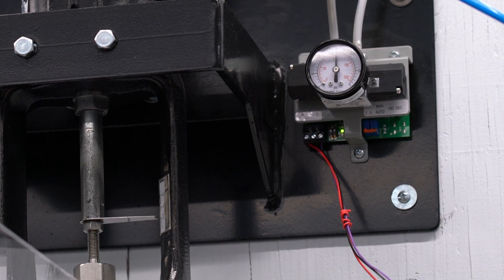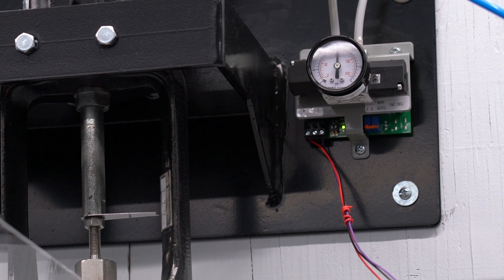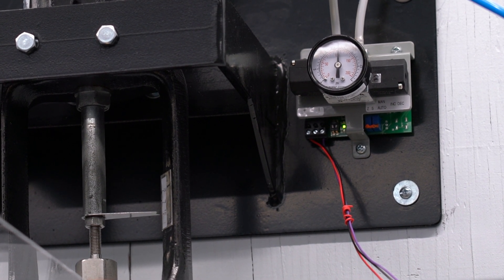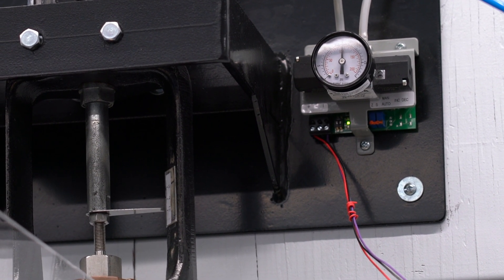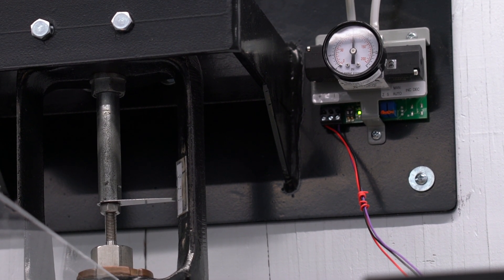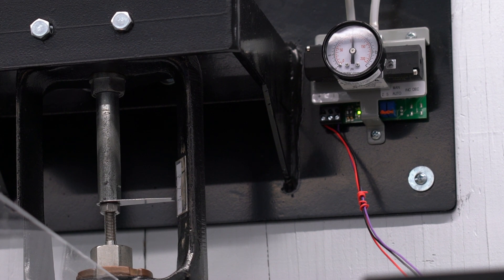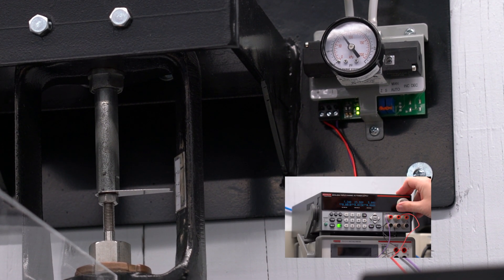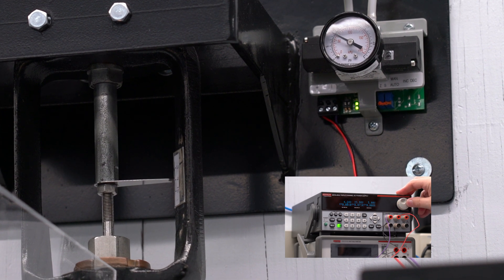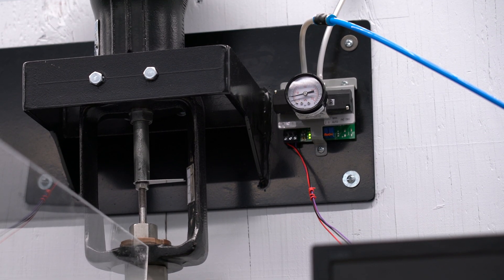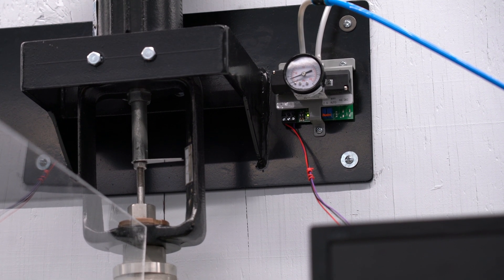Now the other thing is there's a stem with an indicator on the valve that points to the position of the valve, whether it's open or closed. It's a little metal plate that comes out toward the edge of the valve. So when I reduce the voltage, you can see that that's changing position. It's dropping, the pressure keeps going down, and you can see the valve is moving upwards because the pressure is going downwards and there's a spring internally to control that position.